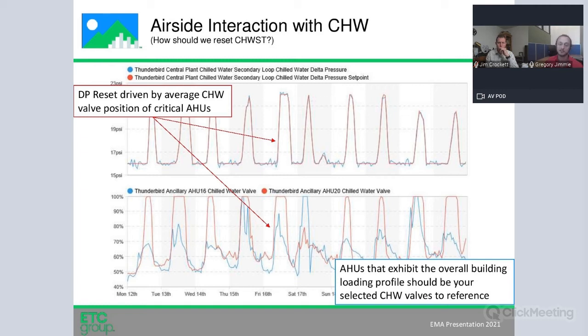For what it's worth, this system is controlling to about a 75 percent average valve position. So as they get above 75, that's when you should expect your pressure to increase. And then subsequently, as they back off in the nights and the evenings, that's when the pressure follows suit and backs off as well. So you're achieving that pumping energy savings in all of these areas on the low end at night and in the morning.